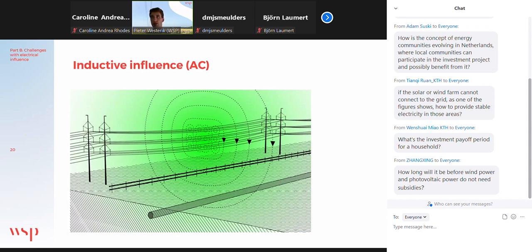Another risk is that when there is a short circuit in the high voltage connection, you will have, for a short duration, if the protection of the high voltage system is working correctly, this can be less than 100 milliseconds, but still it can be dangerous. You have a very high current, which is going in one direction through your electrical circuit, and then it's going into the ground somewhere, and through the ground it is returning to the source. For this very short duration, it generates very high magnetic fields, and you can get much higher voltages on your pipeline. This can be like 2000 volts, even though it's only for 100 milliseconds. Your body could handle it for a very short time, but 2000 volts is still too much, probably. It depends a bit on what type of shoes you are wearing, that kind of thing, additional resistances. So these effects we study regularly.